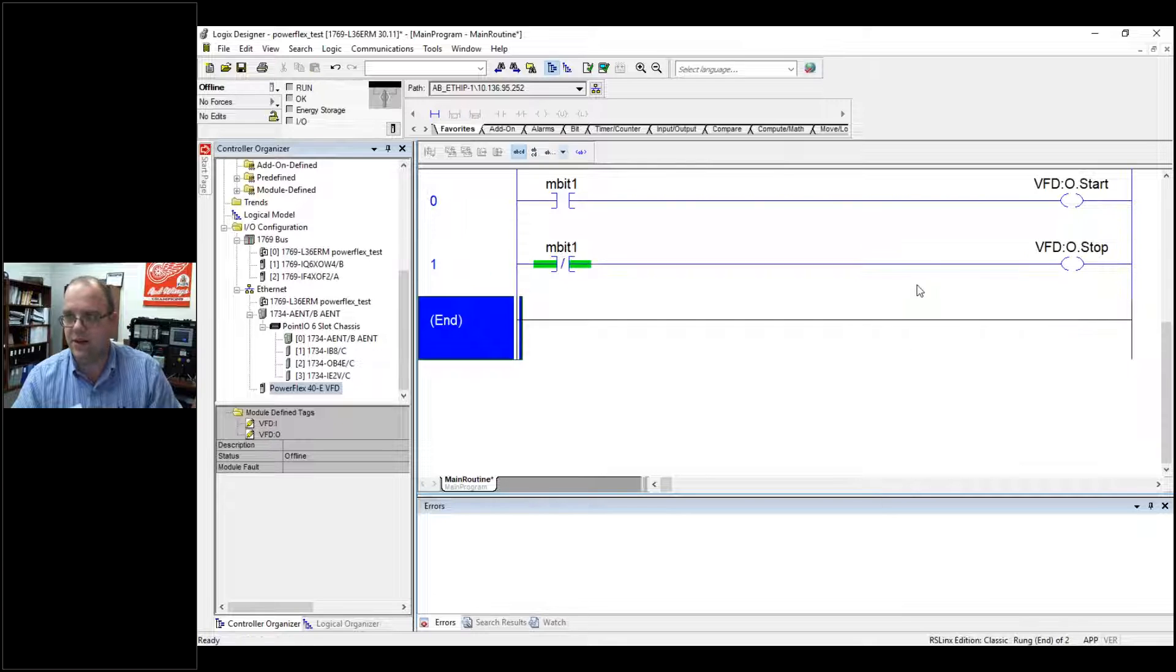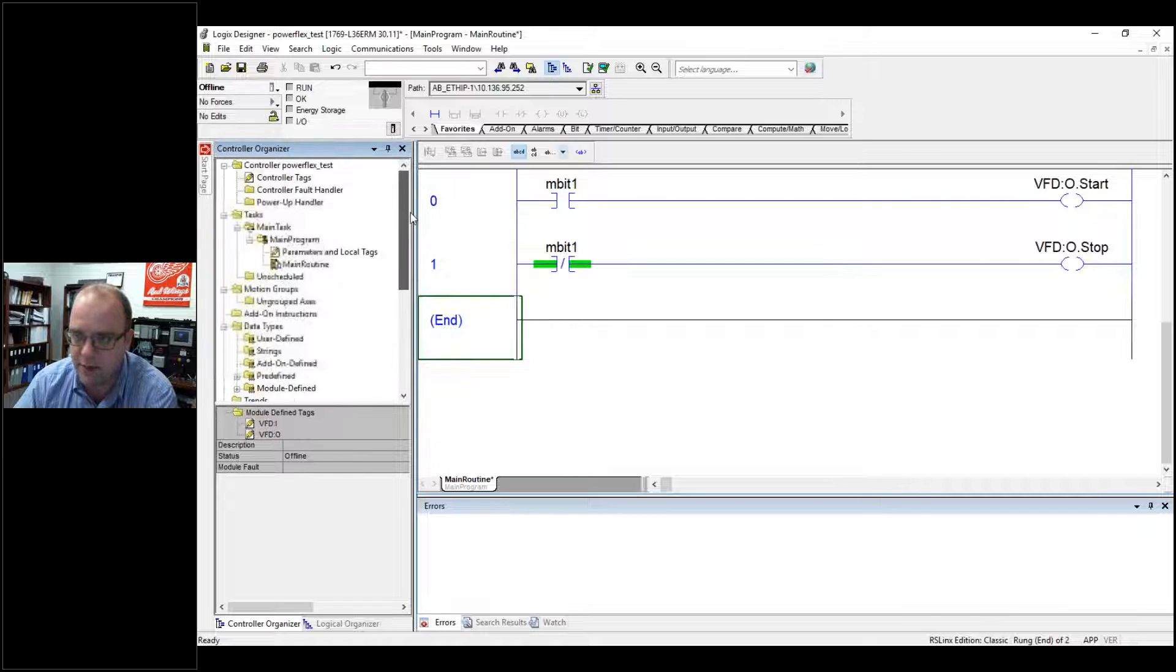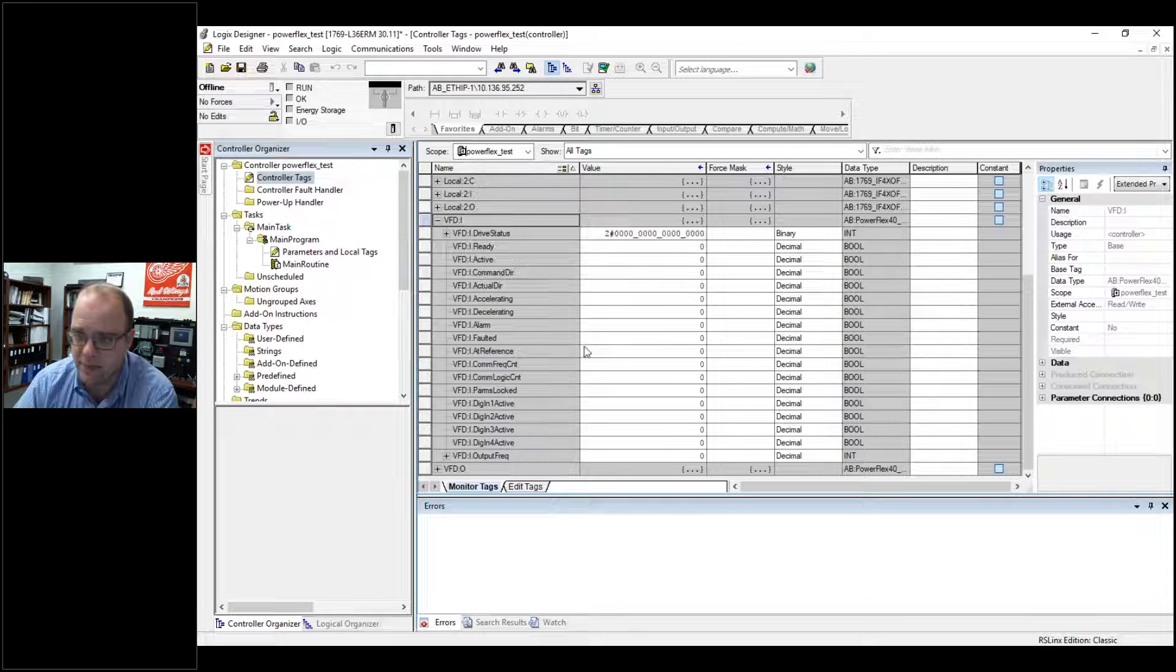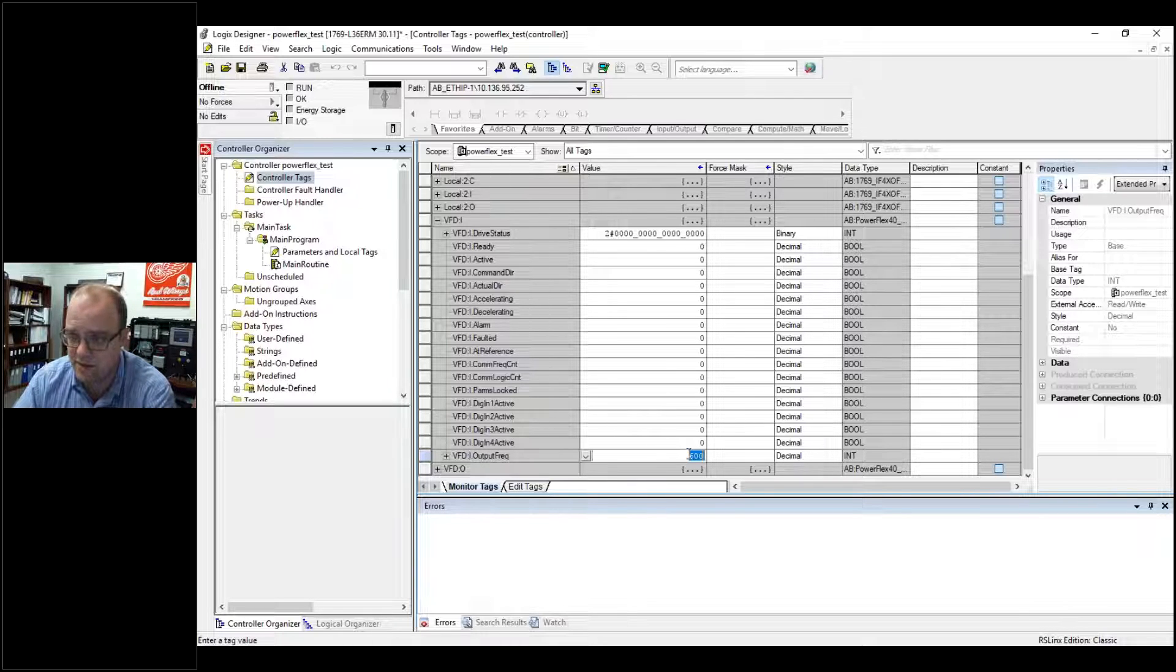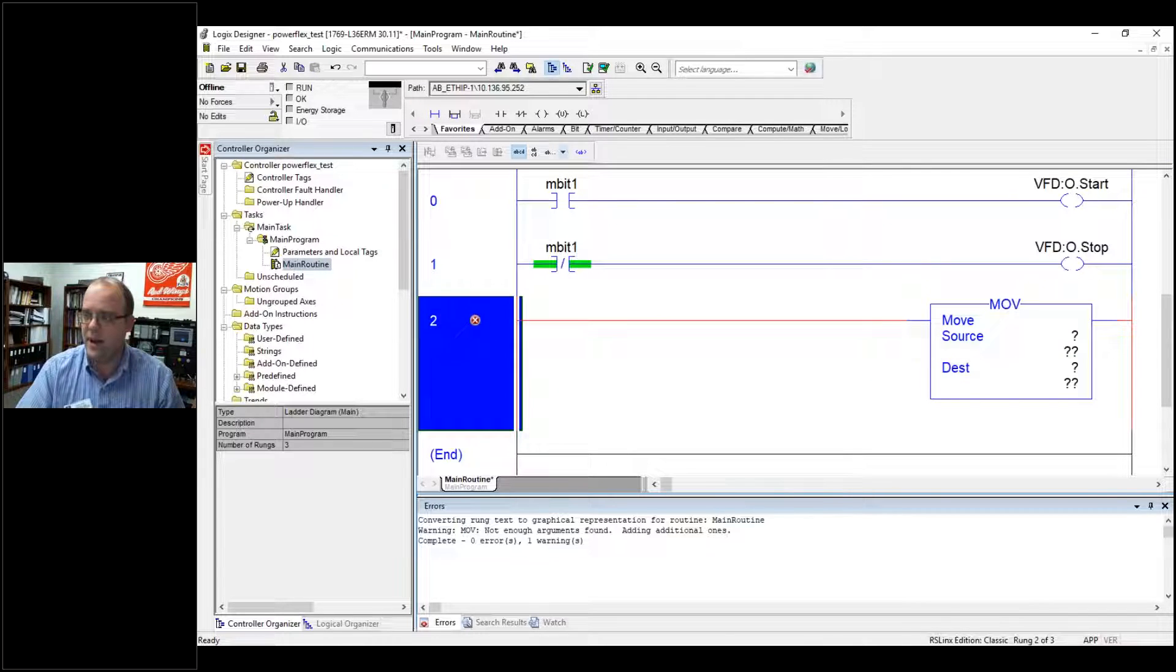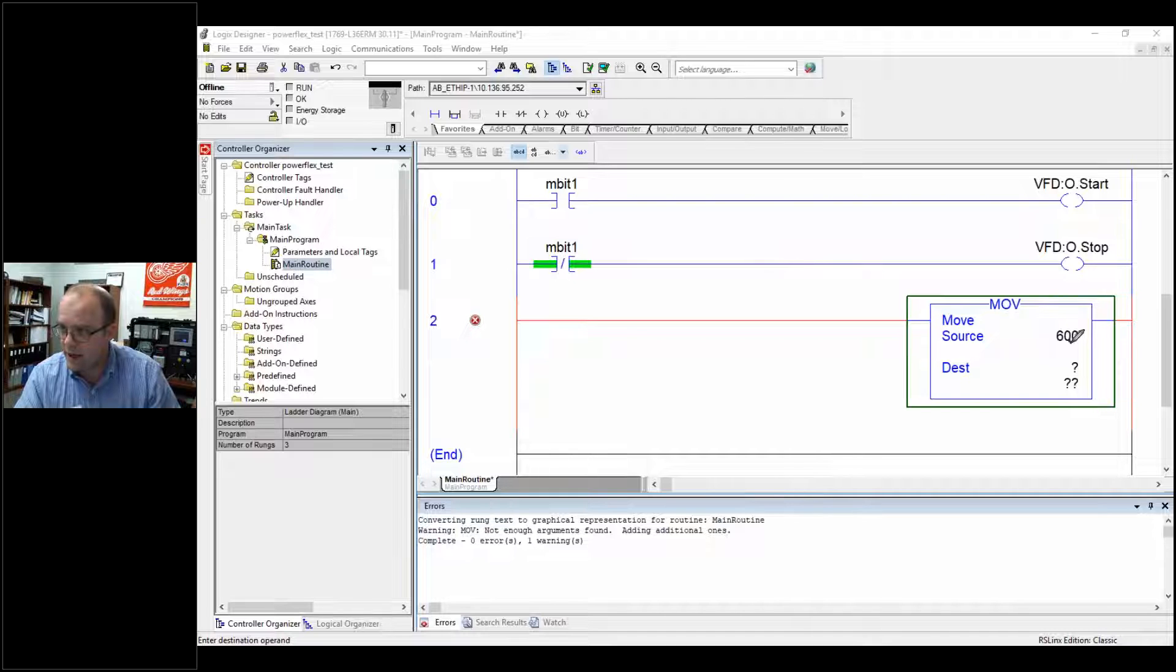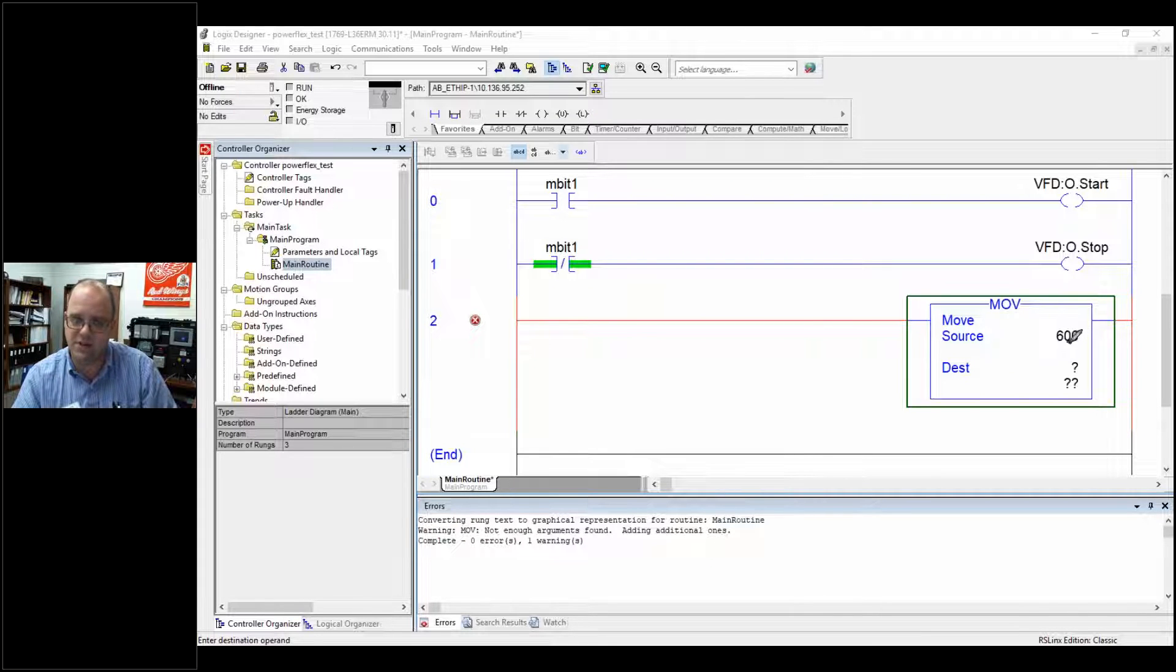And all I need is a momentary input. The other thing you'll need is, you need to make, and I'll go online and show you this, make sure it's set up to point this out. But this is all the program I need to start and stop. I might also want to go into VFD input and make the command frequency, output frequency, and just make that 600 or put a move command to 600. Actually, let me just do that. Just make a move command. And then, even though you may want it to be 60 hertz, there's an assumed decimal point right here when you send things. So when you want 60, you really send 600 because the decimal point's kind of assumed there.